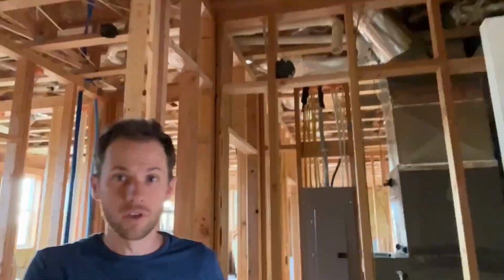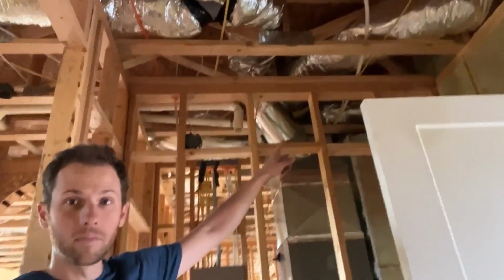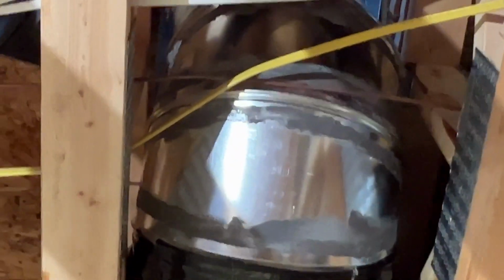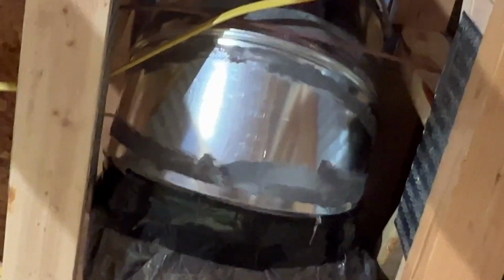Now what used to run through right there runs through the garage instead. We used to have a massive drop down right here in the mudroom; now there's no drop down at all. They said it wouldn't be possible — they said, no, we can't do what you're wanting, you're going to have to have a drop down in your pantry and in your mudroom, and a huge 2-foot one in your basement. But now it comes through a straight metal pipe, a big elbow, and then into the flex, and right into the top of the return box.